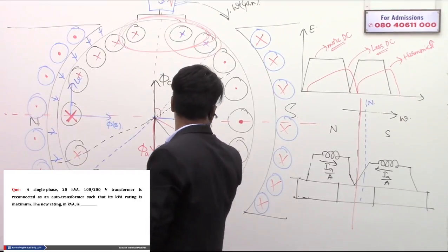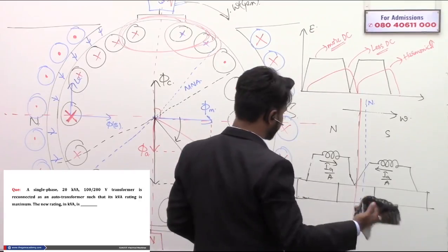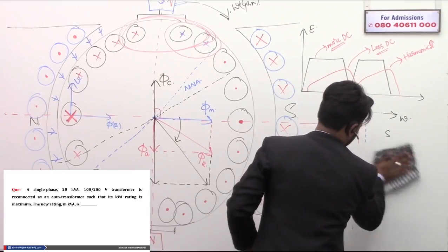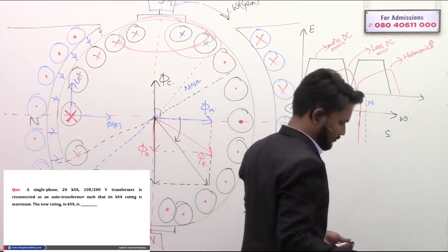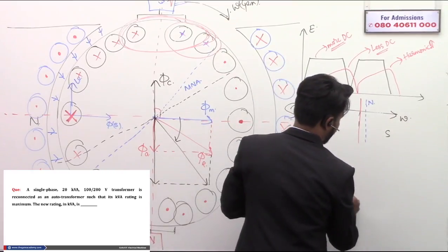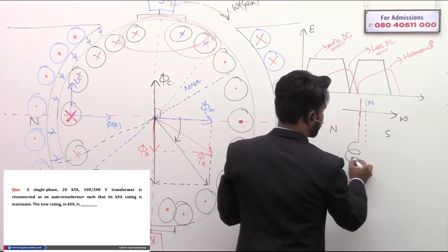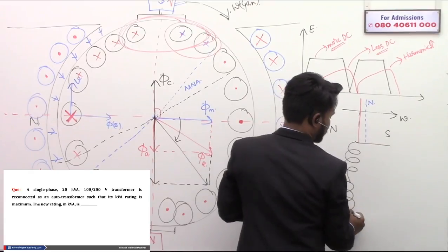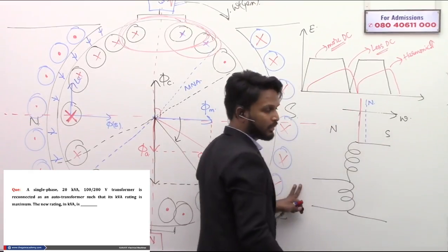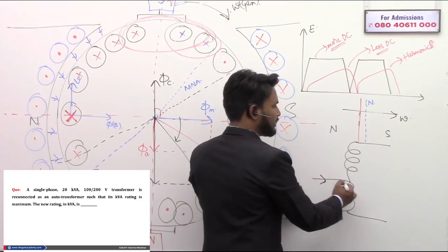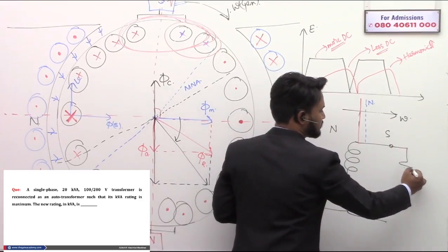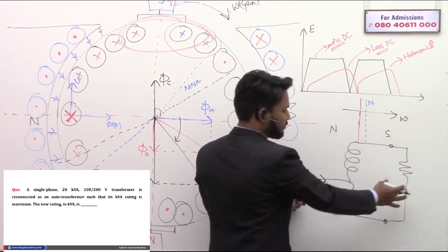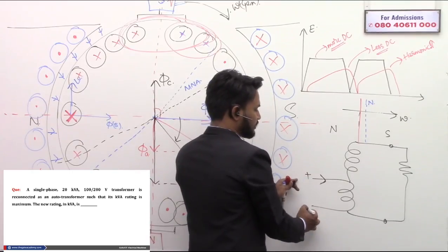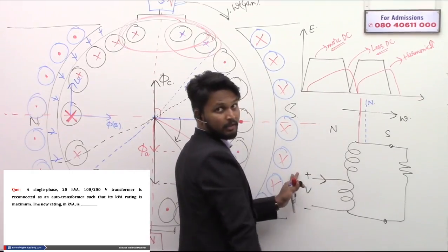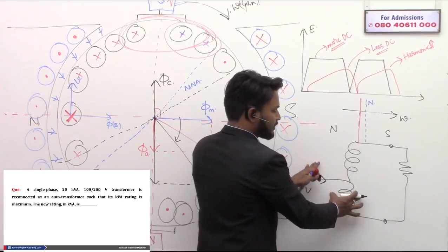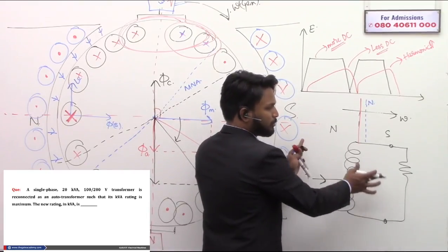See, this is your auto transformer. I'll just draw it here. This is your auto transformer, and this is the load terminal. So this is supplying the entire load KVA that is demanded. Whatever KVA the load demands, that much is supplied from the source. So there is no electrical isolation between secondary and primary.